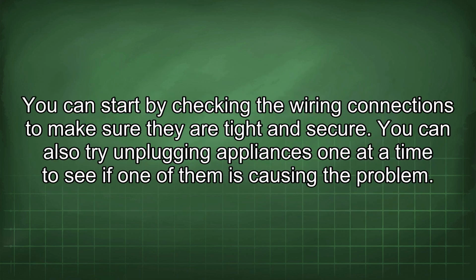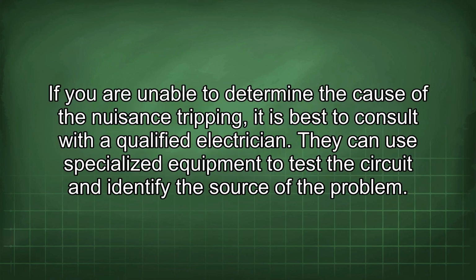You can start by checking the wiring connections to make sure they are tight and secure. You can also try unplugging appliances one at a time to see if one of them is causing the problem. If you are unable to determine the cause of the nuisance tripping, it is best to consult with a qualified electrician. They can use specialized equipment to test the circuit and identify the source of the problem.